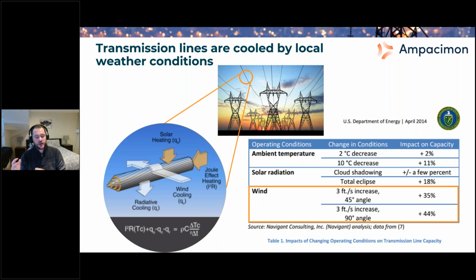If we look at the size or the quantification of these different elements, you can see that ambient temperature, this is from a Department of Energy report a couple of years ago, is approximately a 2% change for a 2 °C change. So that's approximately 1% for every 1.8 degrees Fahrenheit change. Solar radiation has a difference of, if the sun was shining, middle of the day, no cloud cover, versus complete eclipse or middle of the night and nothing else has changed, 18%.